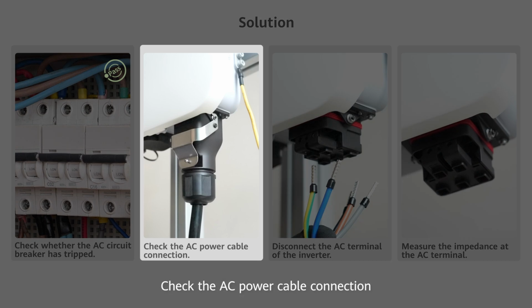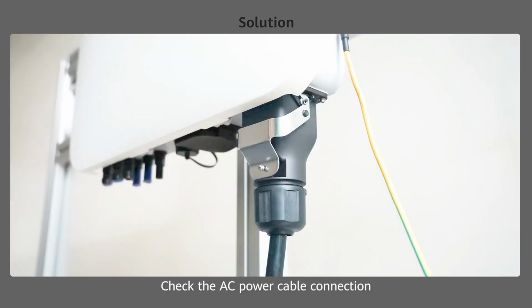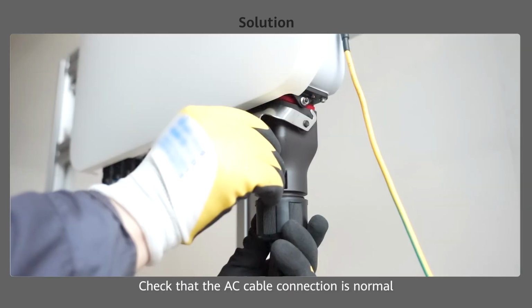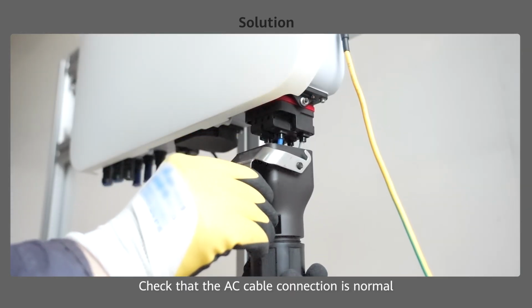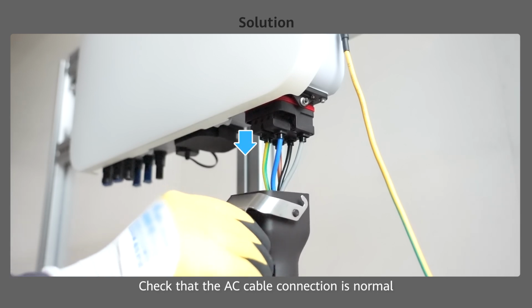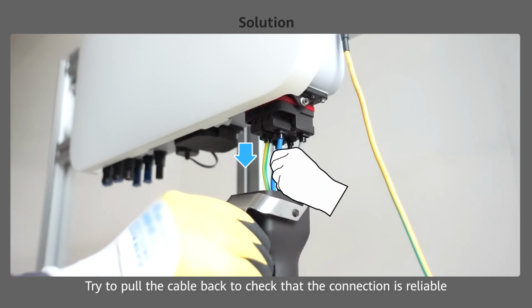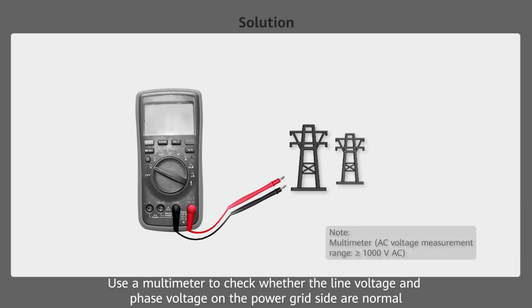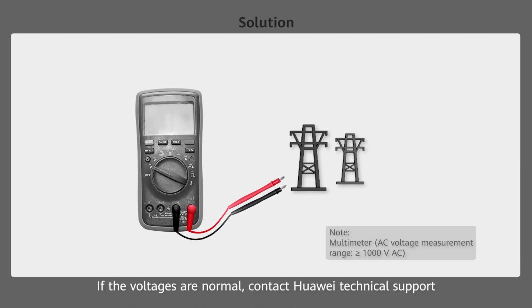Check the AC power cable connection. Check that the AC cable connection is normal. Try to pull the cable back to check that the connection is reliable. Use a multimeter to check whether the line voltage and phase voltage on the power grid side are normal. If the voltages are normal, contact Huawei technical support.